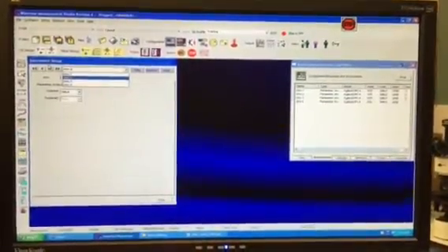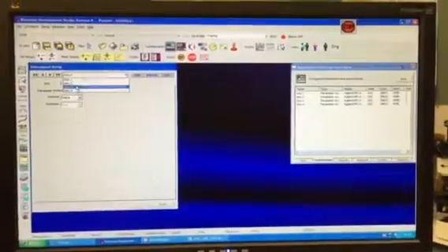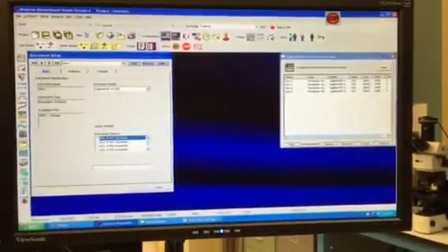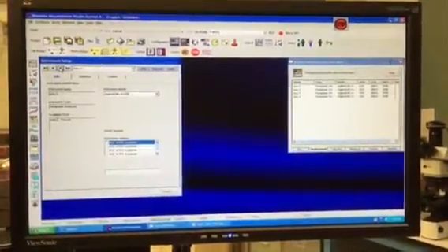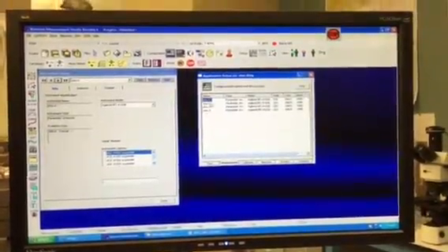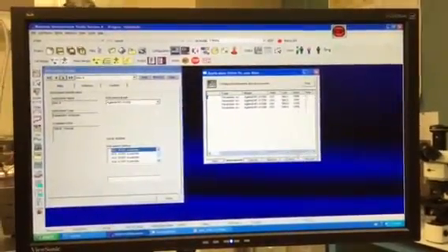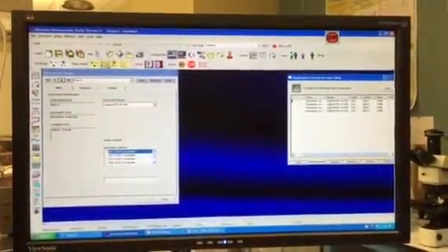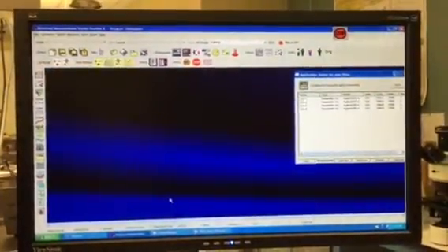So it's up to 4 SMUs? As many as you want. You could have 100, but there's only 4 on that instrument. But you could be adding additional instruments here from other pieces of equipment. So let's say you had a separate power supply, you could add that as well. So I'm going to go back. Clicking here goes back to SMU1. You can see it's 4145 for SMU1, 2, 3, 4. You can also look over here in the application status and see that we've defined 4 SMUs and their addresses, what their output is, and so forth. Okay. So now we have 4 SMUs defined.